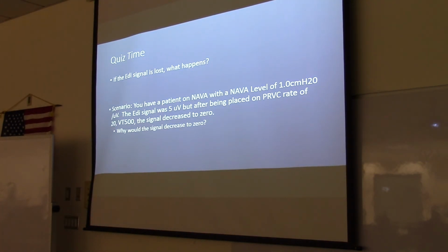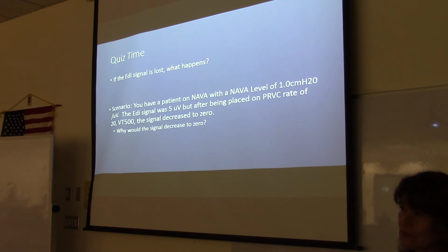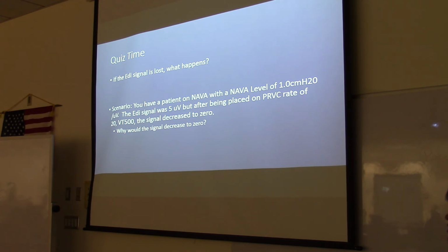There's a scenario: you have a patient on NAVA with a NAVA level of 1.0, or 1 centimeter of water per microvolt. The EDI signal was 5 microvolts, but after being placed on PRVC, rate of 20, tidal volume 500, the signal decreased to 0. Why would the signal decrease to 0? No need to breathe. Too much ventilation. So the ventilator is supplying all the ventilation, the patient doesn't need to breathe above that, so the signal went to 0.